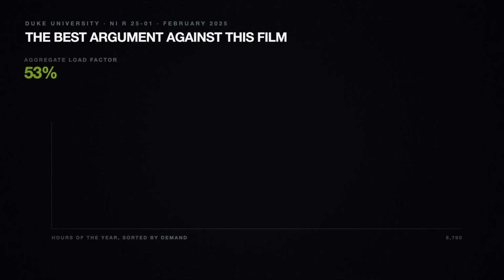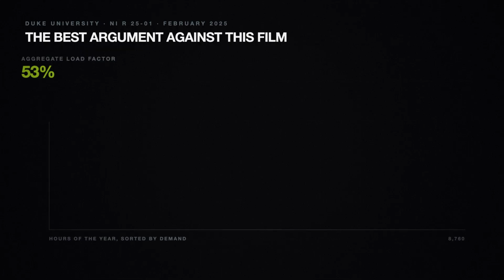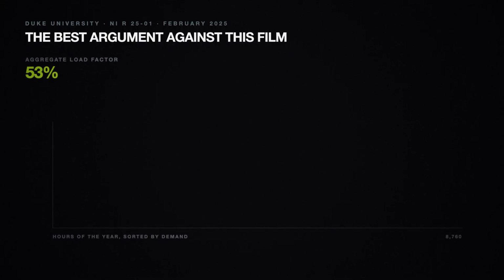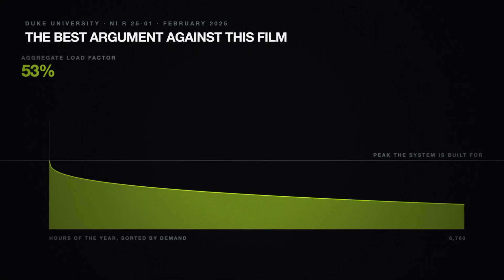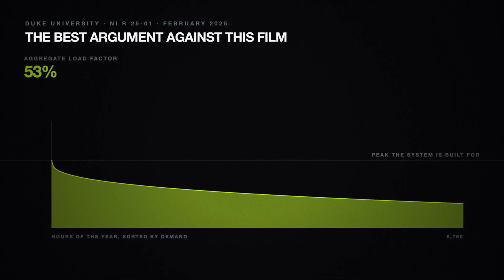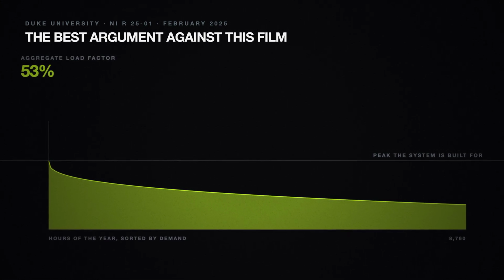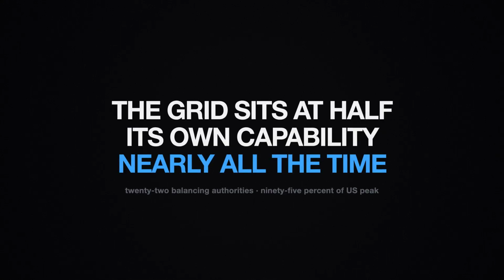In February 2025, researchers at Duke University published an analysis that has since been cited in Congress, at federal regulators, and in state proceedings across the country. Their observation is simple, and once you see it, hard to unsee. A power system is built for its peak. It spends almost no time there. Across 22 balancing authorities covering 95% of American peak demand, the average load factor is 53%. The grid sits at roughly half its own capability, nearly all of the time.